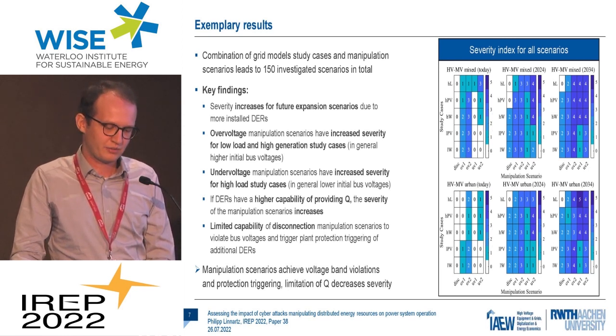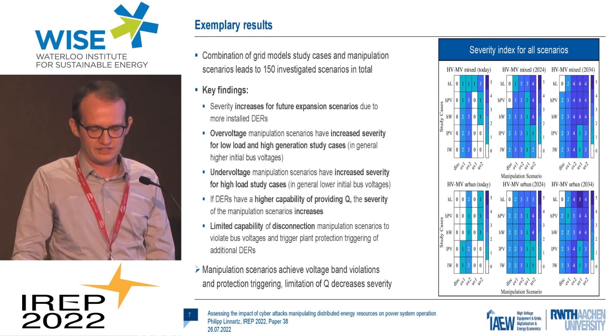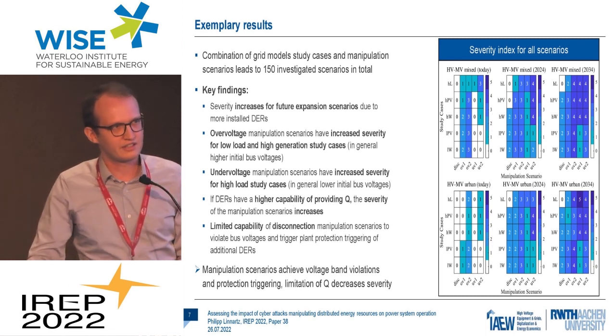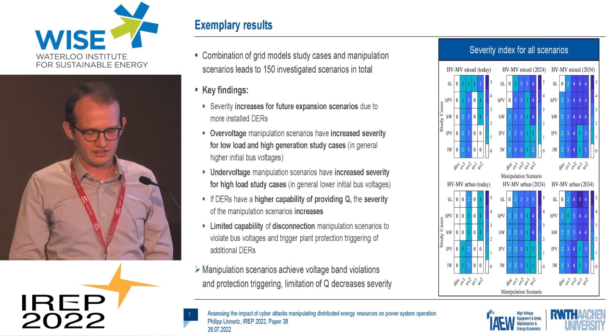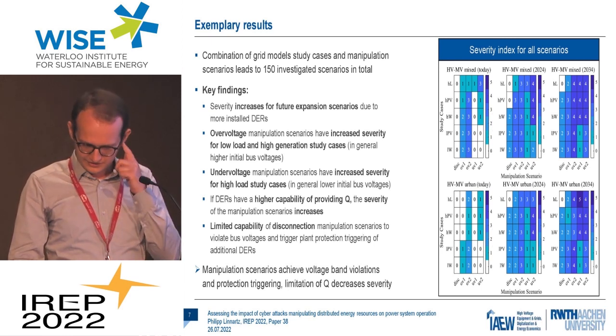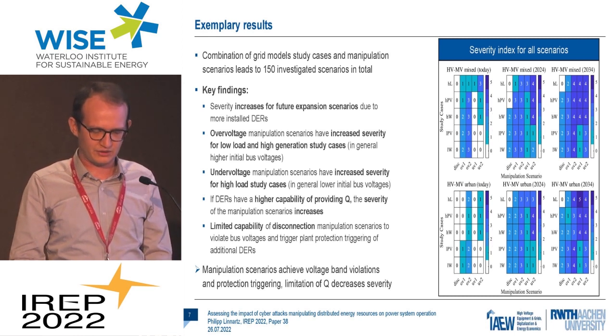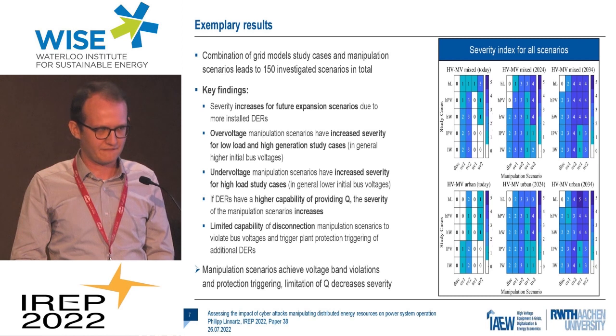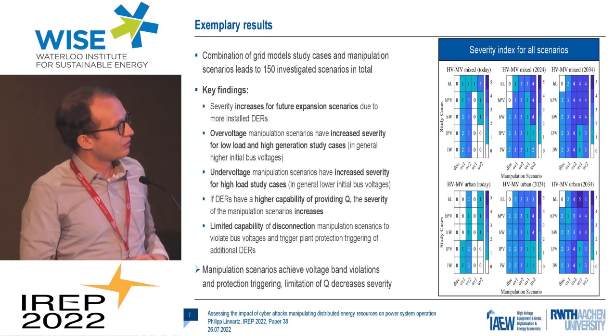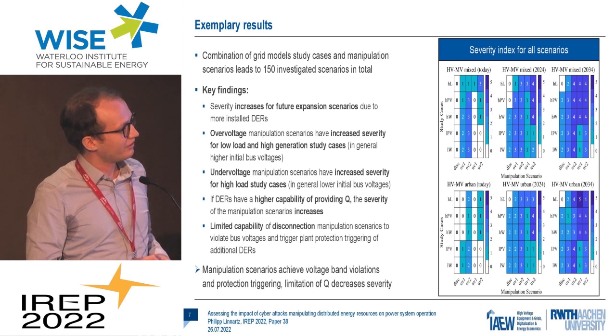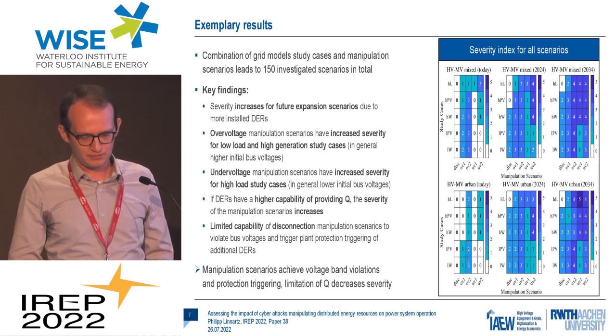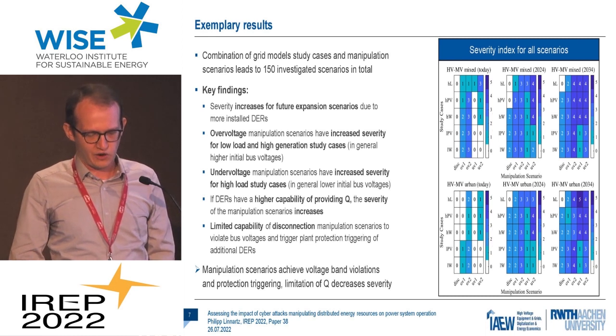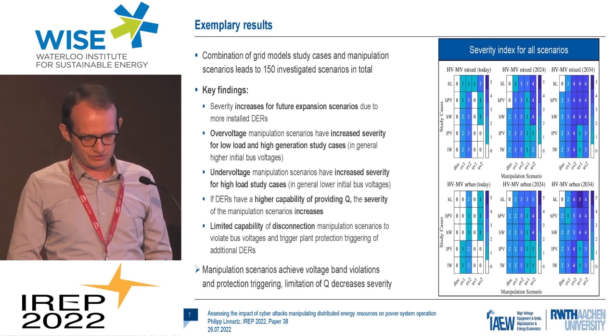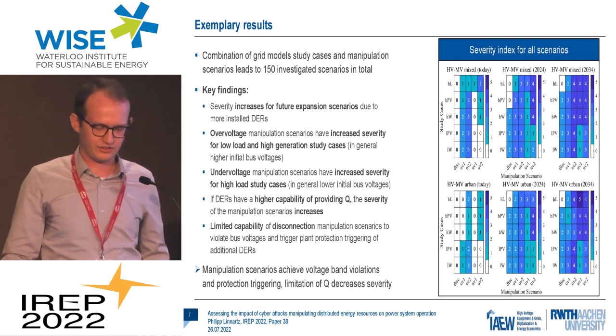Then the overvoltage manipulation scenarios have an increased severity for the low load and high generation study cases, since the initial bus voltages are higher in the beginning. Vice versa for the undervoltage manipulation scenarios, since the bus voltages for high load study cases are lower in the beginning. If you compare these manipulation scenarios, they have an index of 1 or 2. 2 is the one with the higher limits of reactive power provision. If a higher reactive power provision is possible by the DERs, the scenarios are more severe, since the reactive power has a huge impact on the local bus voltages.